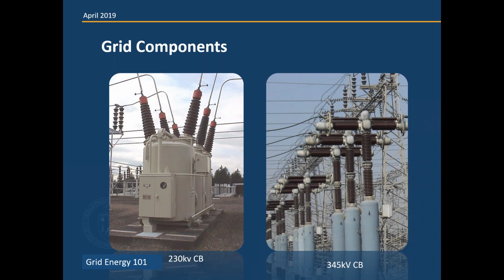So now how does the circuit breaker look on the grid? How does it look in the transmission and substations and power plants? On the left is an example of a circuit breaker. It's a 230 kV oil circuit breaker. And so if you could imagine, there's a game I like to play called Mr. Megawatt. Let's follow Mr. Megawatt down the electrical system, and he comes in from the left there, and it's a three-phase system. That's why we have three of those, actually six of those brown bushings. And Mr. Megawatt comes in, goes through those brown bushings on the left side. He goes through contacts in the circuit breaker, and he pops out on the right, and he goes on down the stream to where he's supposed to go. On the right is a 345 kV circuit breaker, an older style, and the same thing. In this case, he comes in on the left, and he goes through the interrupters and the contacts in the middle, and he pops his way out on the right and carries on down the line. Next slide, please.